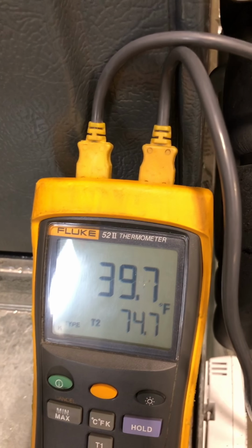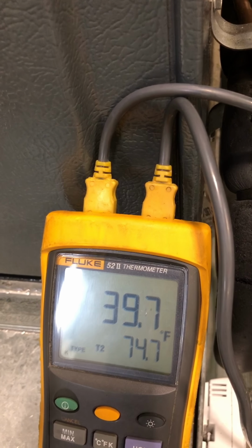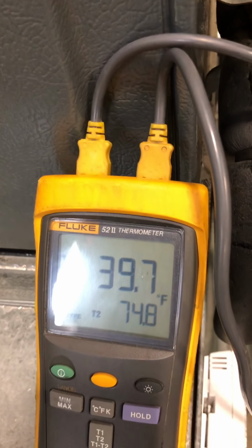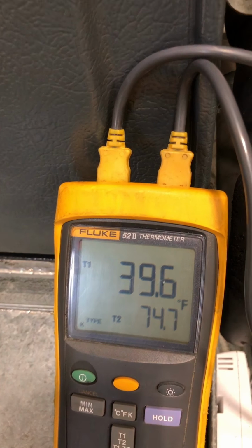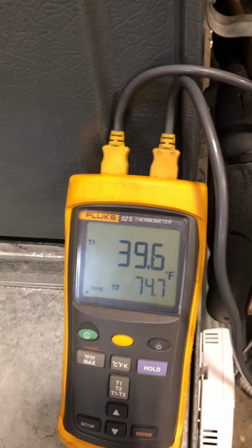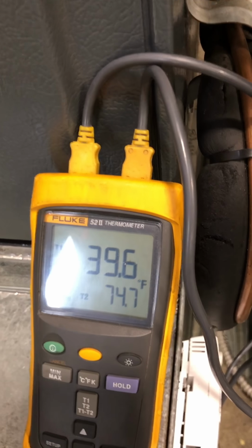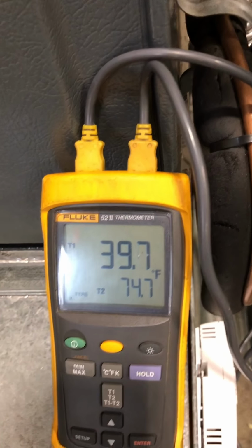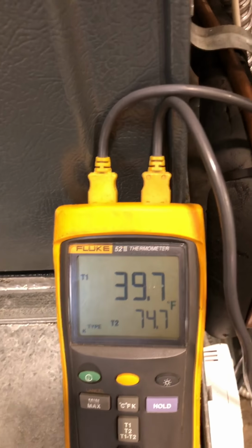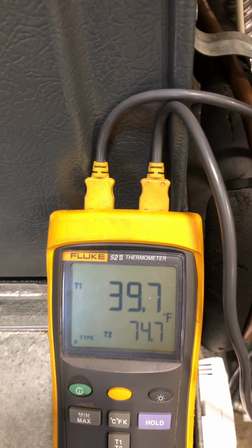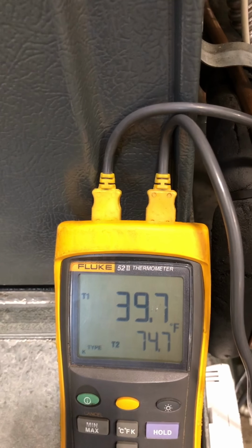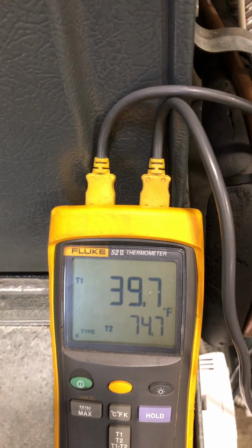That's really not a lot. That's going to be my first red flag right there on this machine. It's really going to depend what the outside ambient is, what's happening inside the house. That will really determine what your superheat actually is. But I want to see that somewhere normally in the 10 to 20 range. And at this point we have 2. That's going to be my first red flag.